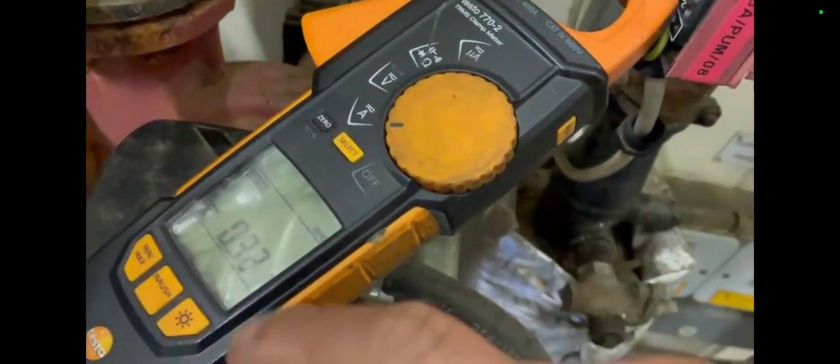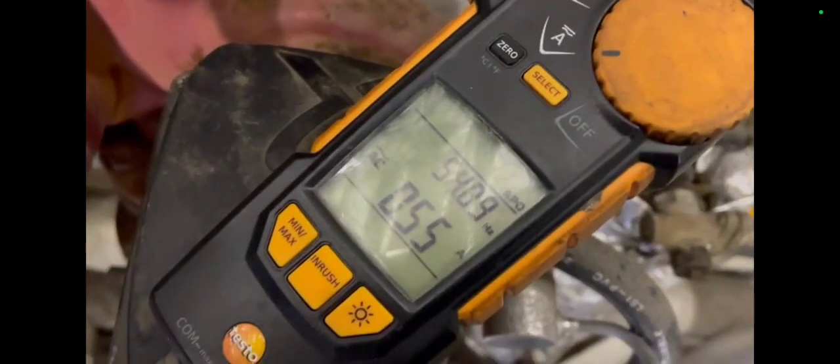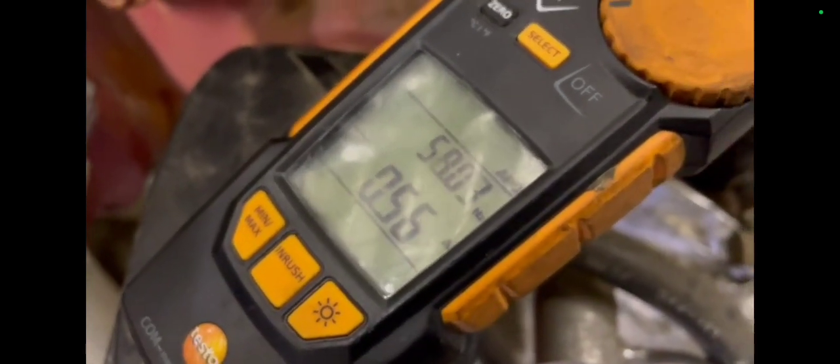I went to the circulating hot water pump to check if there was power to it and if it was circulating. I could see there was a difference in the amps. Unfortunately the control knob did fly off — this pump was in quite a bad state, I could barely see what amps it should be delivering. When I turned the power on I was concerned when it started spraying water across the room, but nonetheless it was still circulating heat around the calorifier.